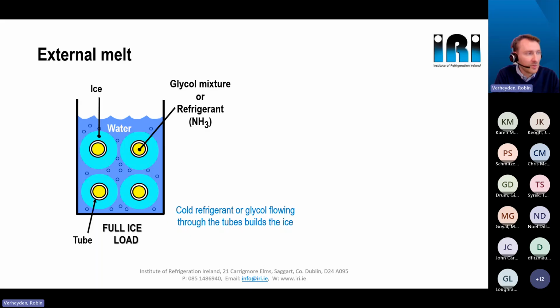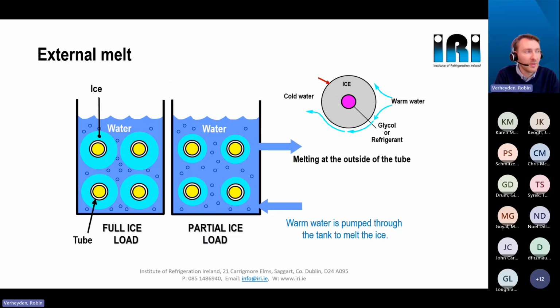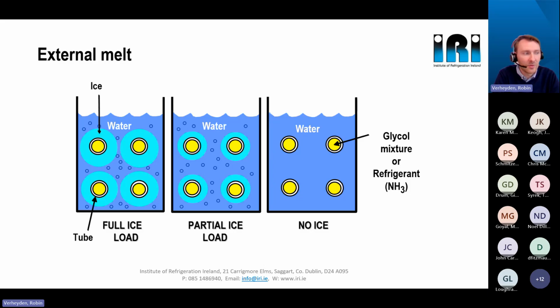So the concept to build the ice is the same as with internal melt. We will build a complete cylinder of ice around the coil by passing cold glycol, or in this case also refrigerant, through the coil. But melting is slightly different. With external melt, we will start melting from the outside. So the water will pass through the tank and will melt this cylinder from the outside to the inside, as you can see also here on the schematic. And at the end, the same, we will end with a complete tank full of water. It's important to melt down your complete ice tank once a week, max 2 weeks. This is just to prevent some parts of ice from staying in the ice tank, so that later, when you start building the ice again, you have a uniform ice build, because otherwise this can give additional stretching or pressure on the coils.